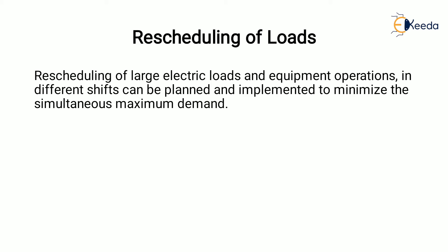Next is rescheduling of loads. Rescheduling of larger electrical loads and equipment operation in different shifts can be planned and implemented to minimize the simultaneous maximum demand. For this, we need to prepare an operational flow chart and a process chart so that it can be analyzed. After analyzing, it would be possible to reschedule the operation and running of equipment in such a way that it improves the load factor, which in turn will reduce the maximum demand.